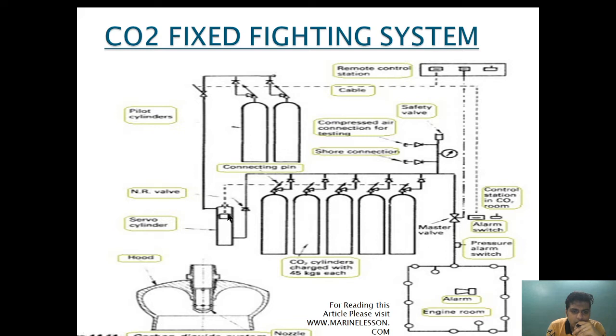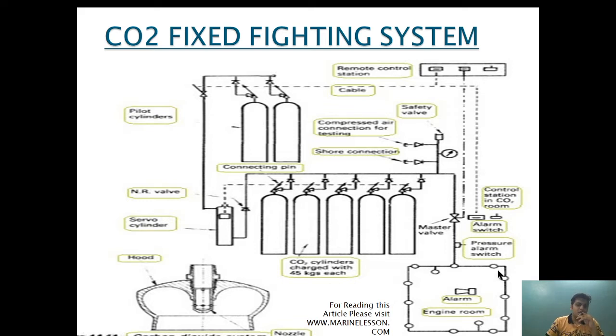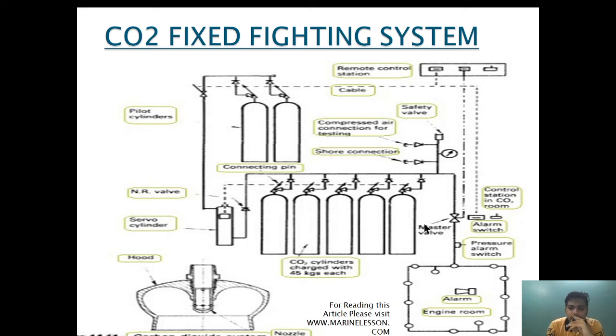The connecting pin is provided in such a way that when it is pulled by the wire it will puncture the individual CO2 bottle, causing the gang release of CO2 from the system, which will be collected in the pipe. The CO2 from the pilot cylinder pushes the servo cylinder down, and as the servo cylinder is pushed down this wire causes the connecting pin to puncture the CO2 cylinder. The CO2 then goes to the master valve, operated by the remote control panel, and depending on the section — purifier room, engine room overhead, or engine room — the CO2 is directed accordingly.